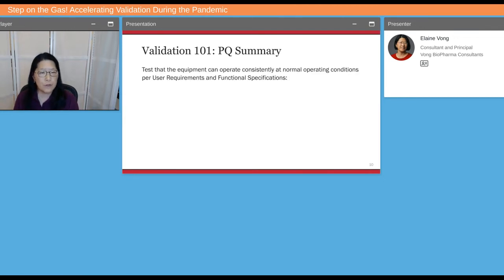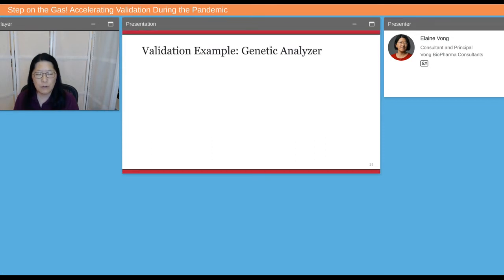For the PQ summary, test that the equipment can operate consistently at normal operating conditions per the user requirements and functional specifications. This may include using the number of personnel and operators that will be in the facility at the time, materials and commodities that are used in manufacturing normally, the environmental conditions of temperature, humidity, etc. that are required, as well as using your approved standard operating procedures.